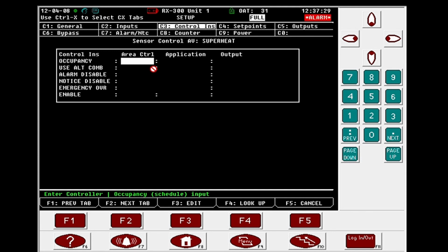Say you wrote this to monitor the floating of the circuit. Say the circuit's not floating or the superheat's too low. You could disable and enable the alarm to only alarm during business hours. That way you can call a technician out, not on overtime, but on straight time. I mean, this stuff you don't need for everything. This is just basic stuff.